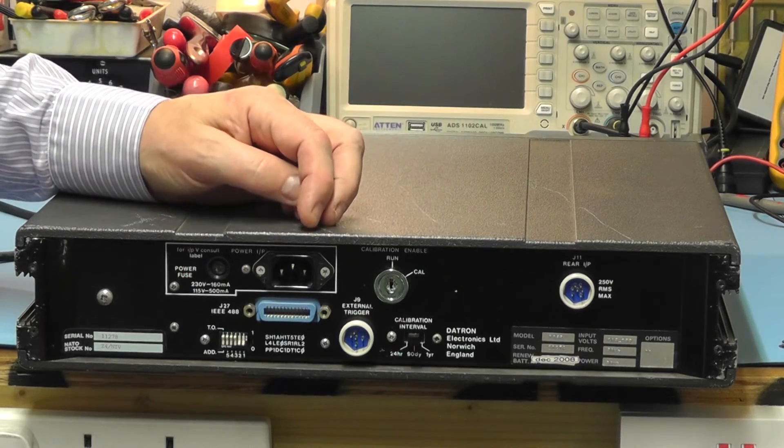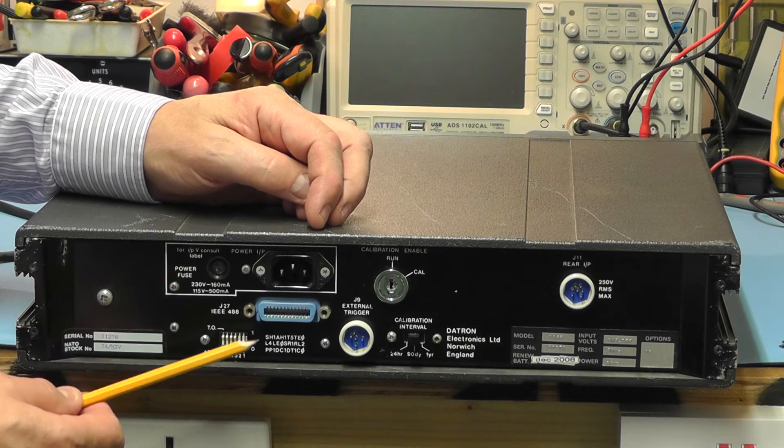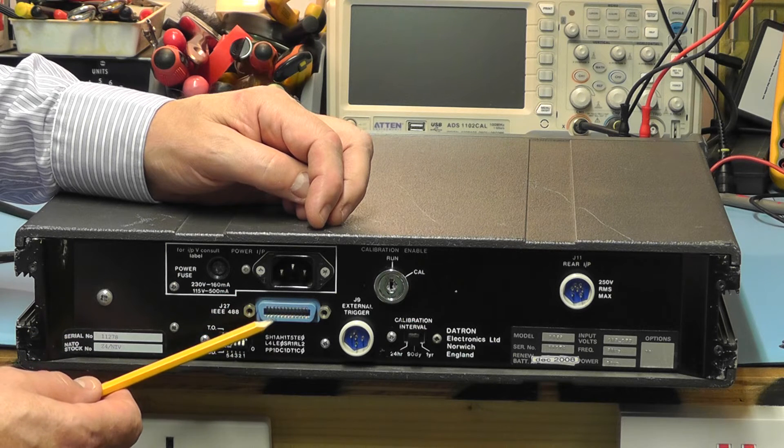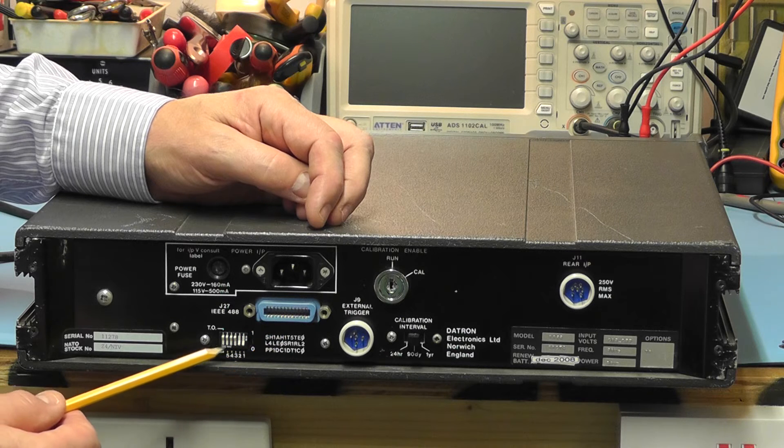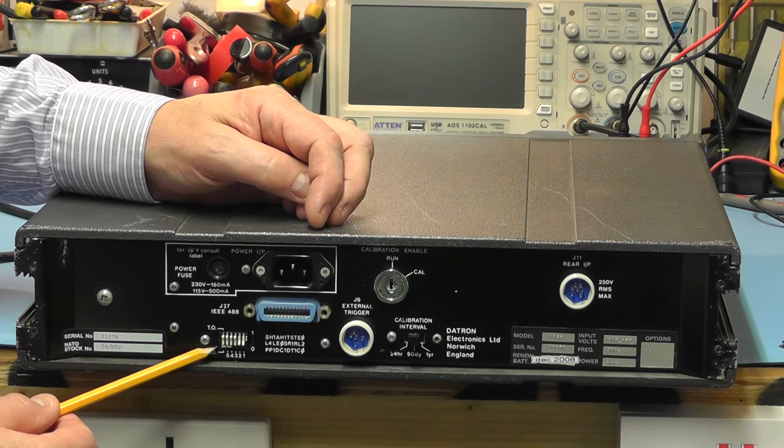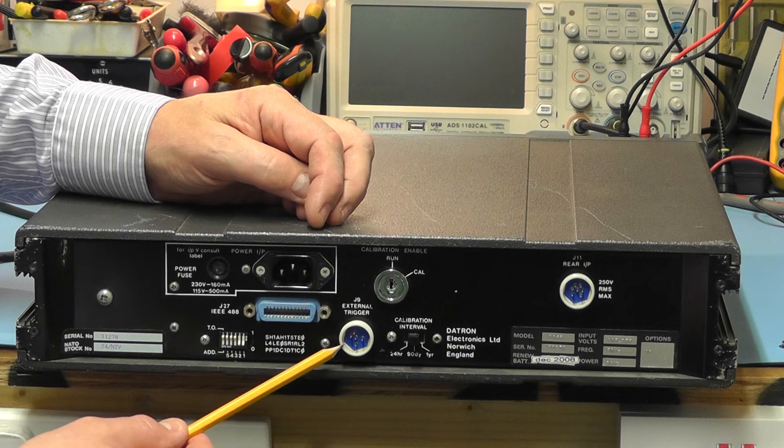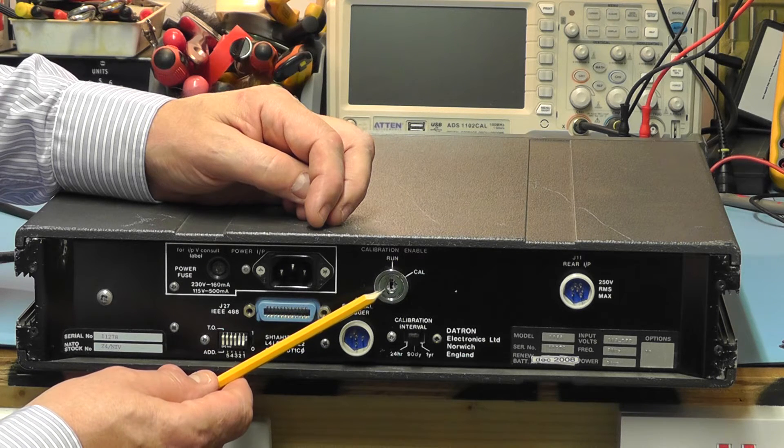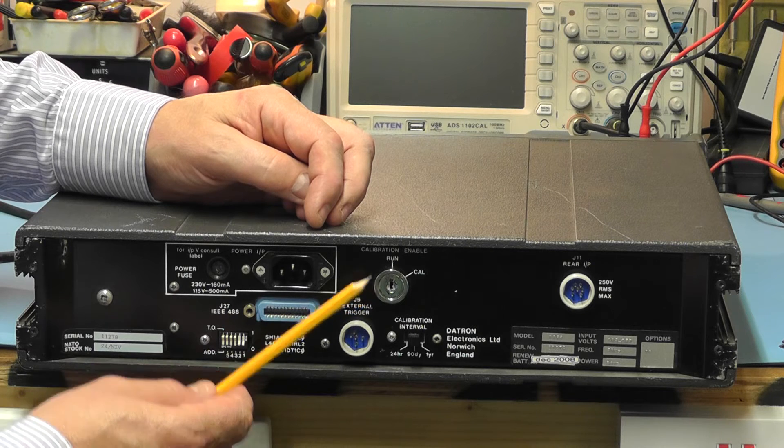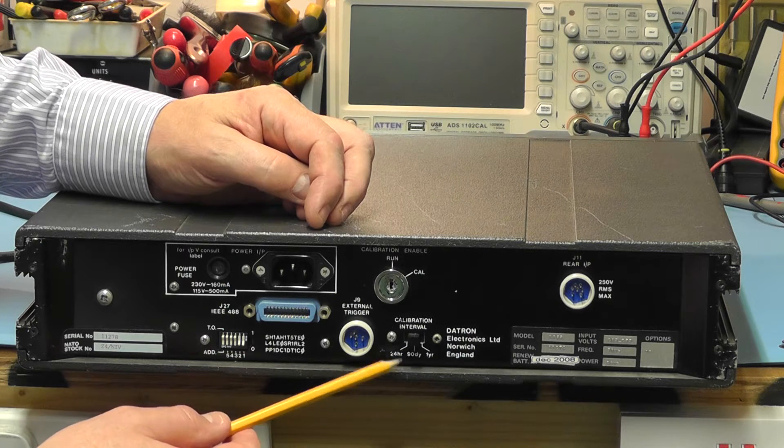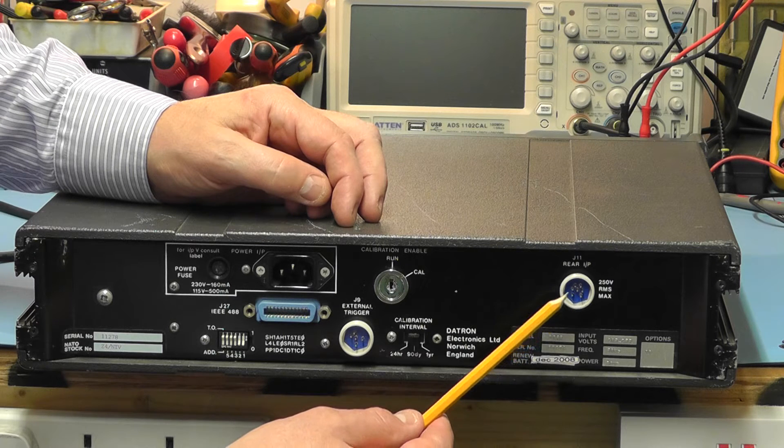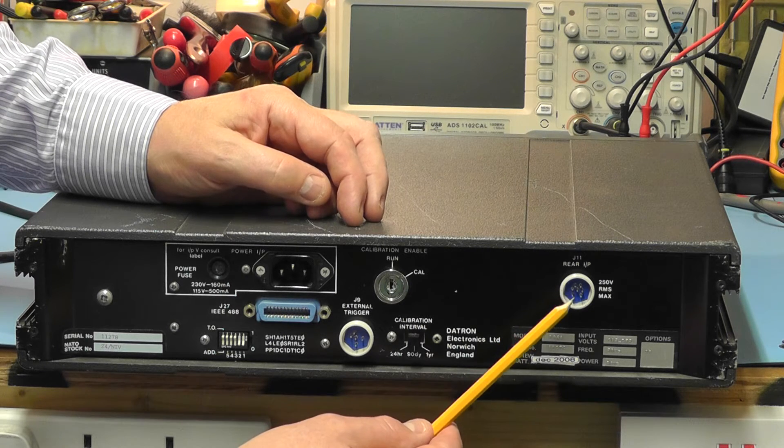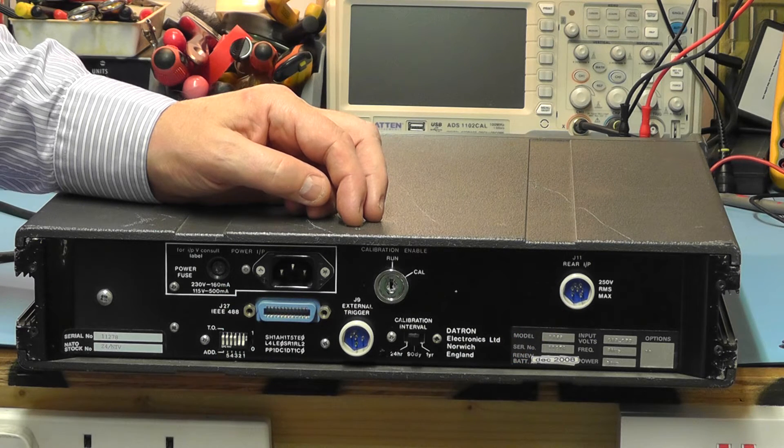At the rear of the unit we have the mains input connector and the input fuse. Here we have the GPIB connector with the IEEE488 standard and the address can be selected by this DIL switch here at the bottom. This socket here is used for external trigger. The key switch here is used to switch it into calibration mode and we have another switch here which is a calibration check switch labelled 24 hours, 90 days and one year. The right connector is the rear input connector for the main leads to the meter.